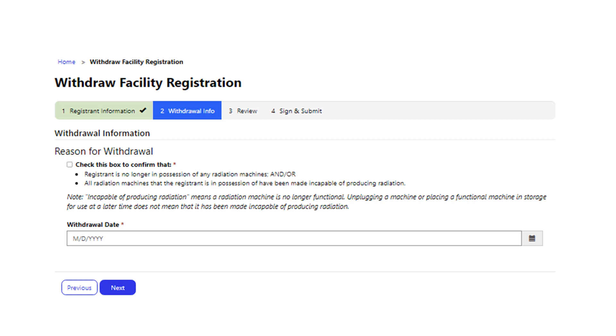Section two is the withdrawal information. It is important to click the box to confirm that the registrant is no longer in possession of any radiation machines, and/or all radiation machines that the registrant is still in possession of have been made incapable of producing radiation. You will not be able to move forward if this box has not been checked. Once that is done, enter the date of the withdrawal. Please note this cannot be a future date.